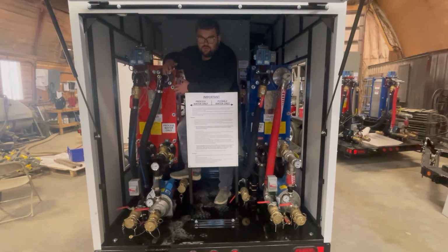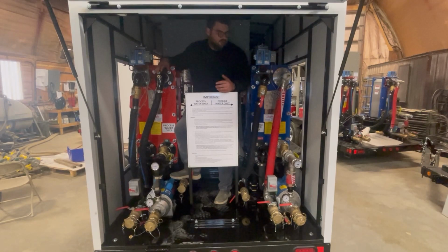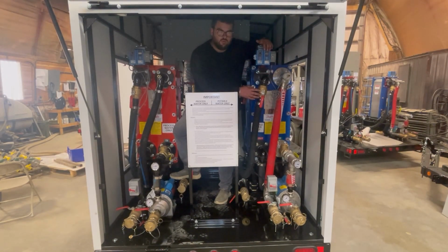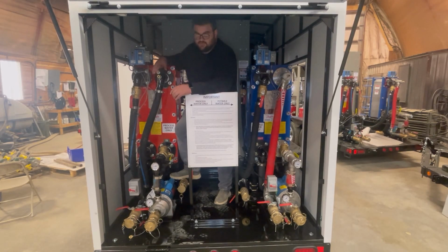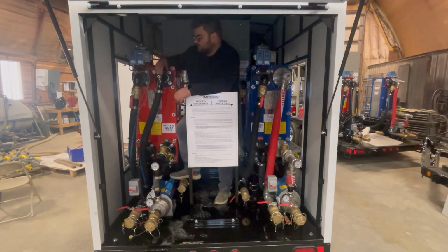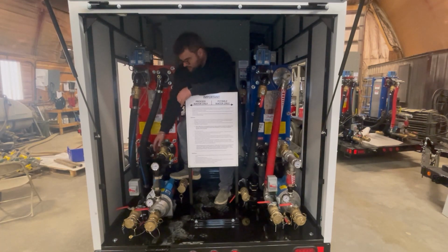On the rear of the unit, we have 2 plate heat exchangers. They're nearly identical, however, the blue unit here is potable water, and the red unit is processed. So we have a couple different fittings between the two, but the operation of them is identical. We have a 3 horsepower pump, identical to the one on the glycol side for each plate, as well as glycol in, glycol out, your water in, and your water out.